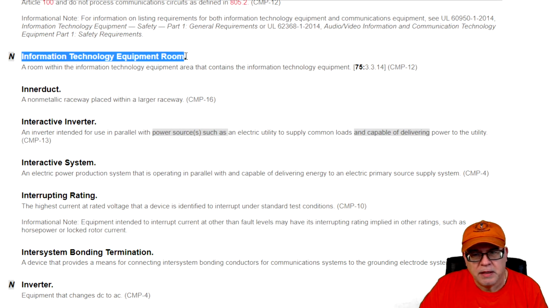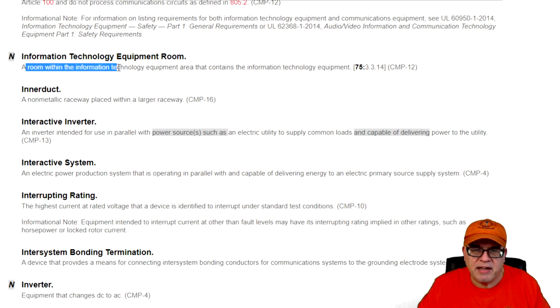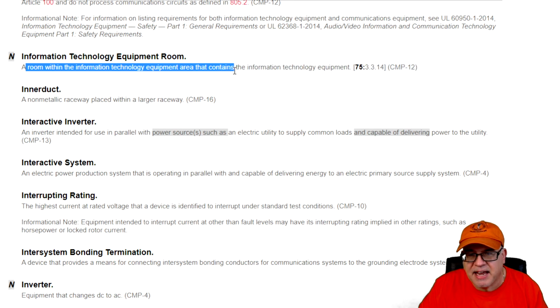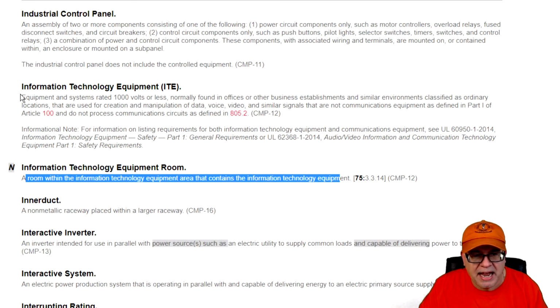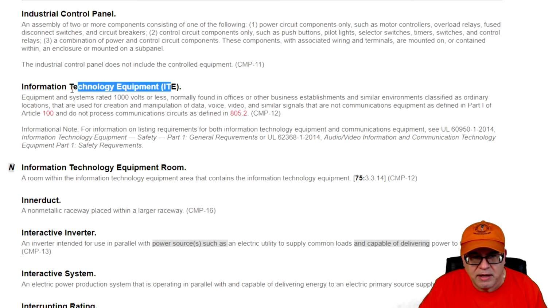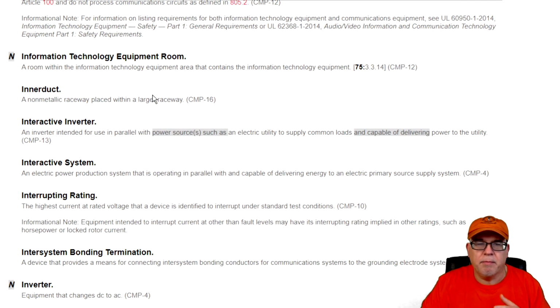Information technology room. The reason we talk about this one is because you'll have a 645 that talks about IT rooms and things like that. So what is an information technology equipment room? It is a room within the information technology equipment area that contains the information technology equipment. And of course, we have information technology equipment right here, and that talks about the specific equipment that we're dealing with. All right, so the equipment room is inside of the information technology area, and it's a space just for that IT equipment, okay? And instantly, it's a good time to explain this right here.